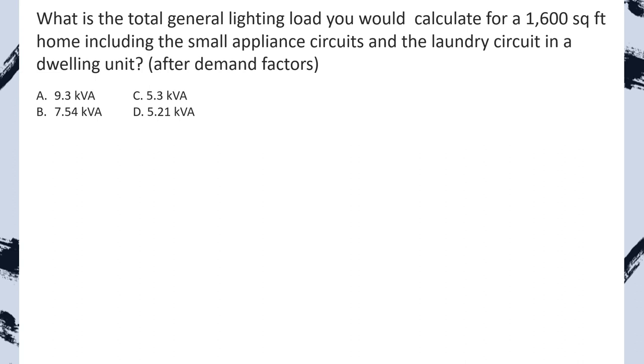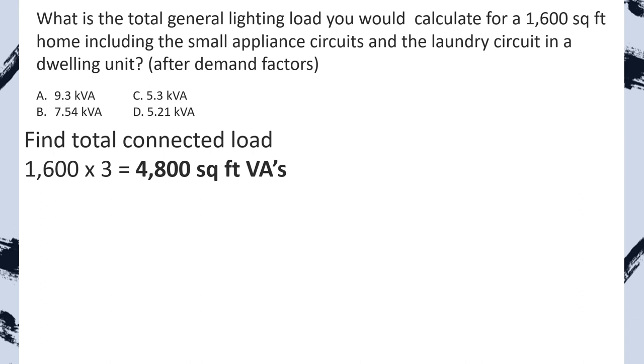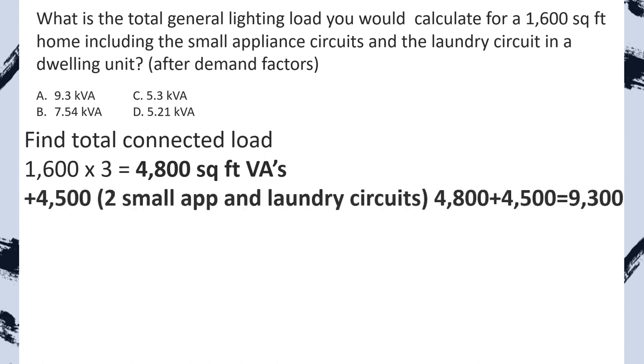In this question, I went ahead and stated that there are two small appliance and one laundry circuits in the dwelling unit. From now on, I'm not going to state it anymore for the questions, because on your examination they're not going to state it either. You just have to know anytime you're calculating the total general lighting or doing a whole home load calculation, you have to include the two small appliance and one laundry circuit, which equals 4,500 VAs. Step one, find the total connected load: 1,600 square feet multiplied by three VAs per square foot gives us 4,800 VAs. Now we tack on our 4,500 for the two small appliance and one laundry circuits, giving us a total of 9,300.